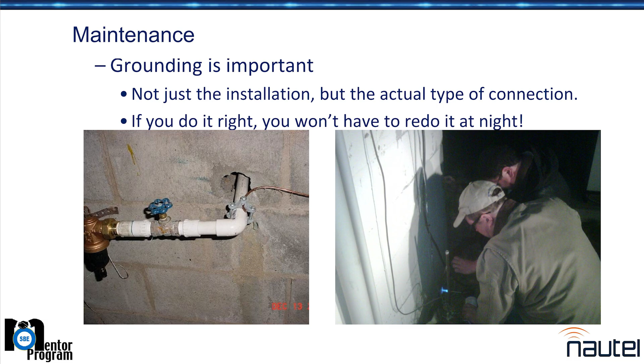It's really hard to get a Cadweld mold for copper strap, so braze it, silver solder it, silphos, I don't care, but use an exothermic connection. Do not just hammer it over flat and call it good enough, because copper is malleable and will deform, and it will also oxidize, and now you've got a resistor. Remember the current divider game: the lowest resistance we can make the preferred path, the better.